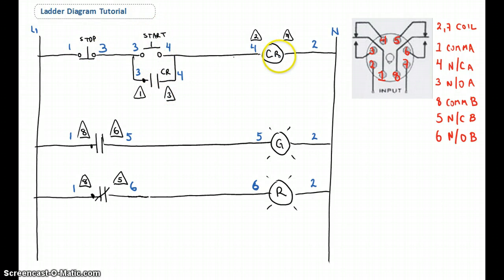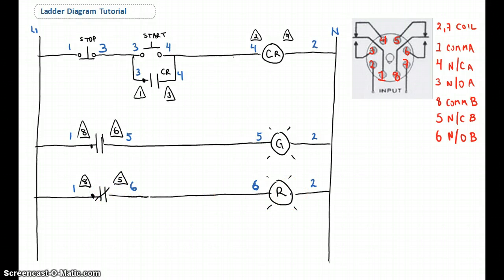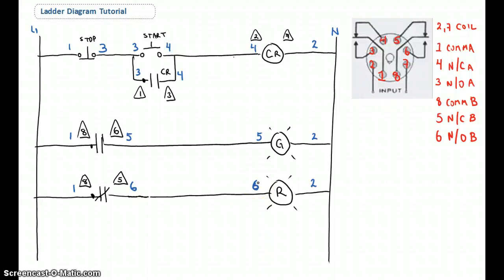We've got all of our components: the stop, the start, and the control relay coil at pins 2 and 7. Pins 1 and 3 denote the normally open holding contact; we didn't use pin 4 since the stop push button handled that. When the control relay turns on it closes the green light contact and opens the red light contact. When de-energized, the red light turns on and the green turns off. At this point if you needed to expand this circuit further, we're essentially out of contacts on this relay.